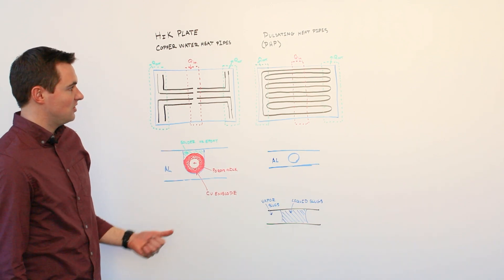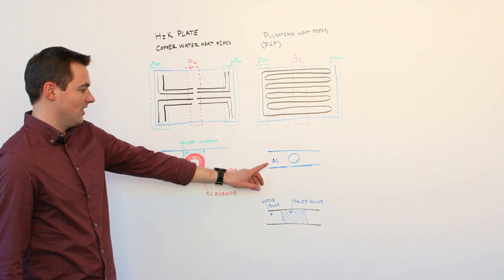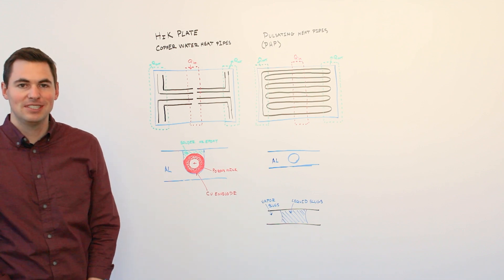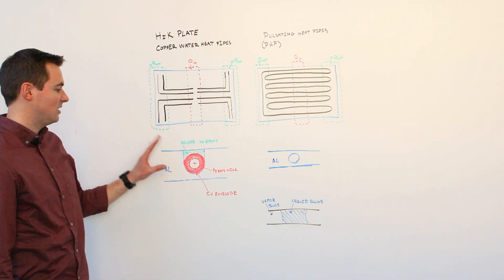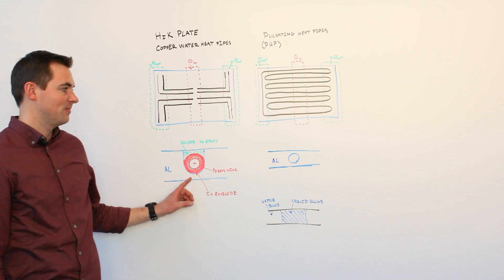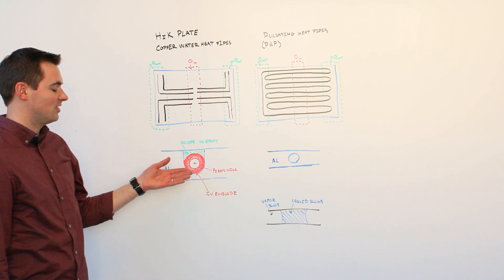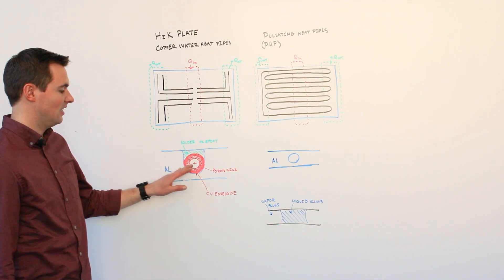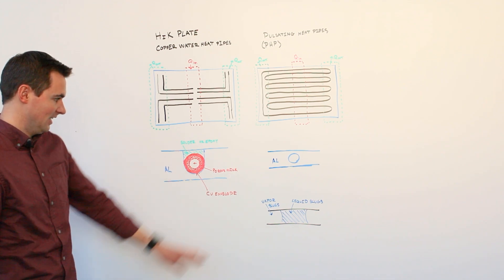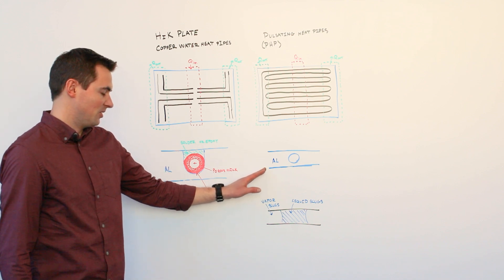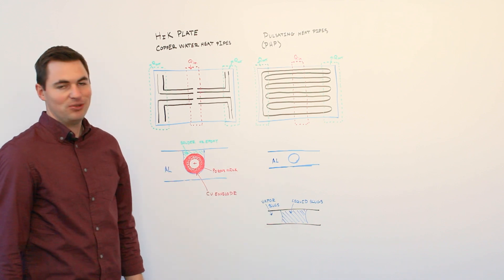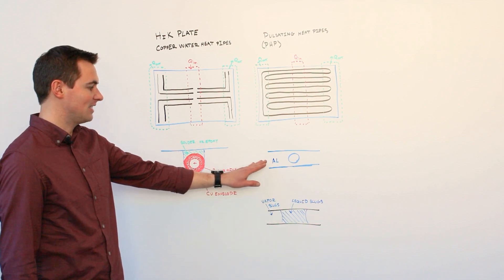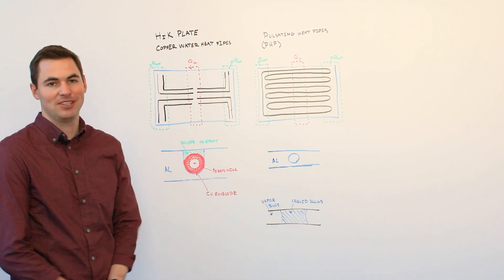Another reason you may choose a pulsating heat pipe is that this configuration can be compatible with many working fluids, whereas copper water heat pipes typically use water as the working fluid. So for applications where temperatures are below zero and there's a likelihood of freezing with water as your working fluid, pulsating heat pipes are compatible with many other working fluids such as ammonia or alcohols or refrigerants. So for space applications or other applications where you're looking at cold temperatures, pulsating heat pipes may be a good option.